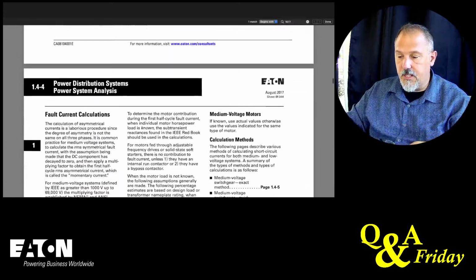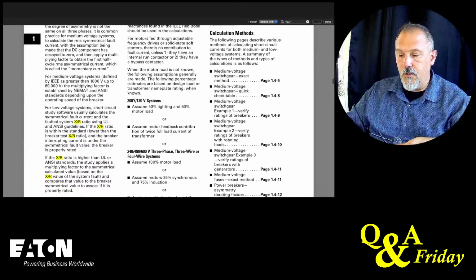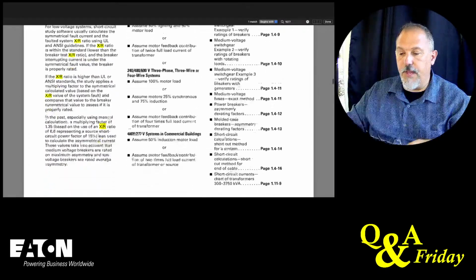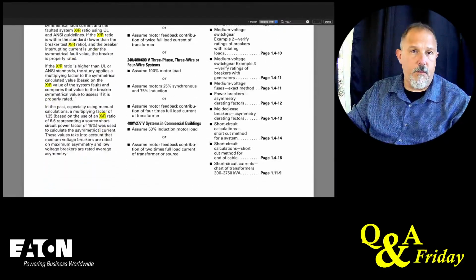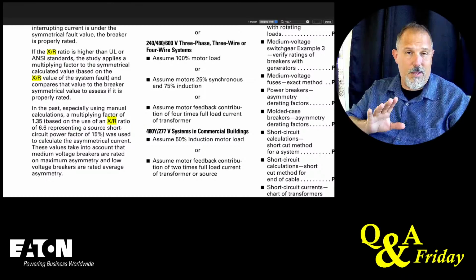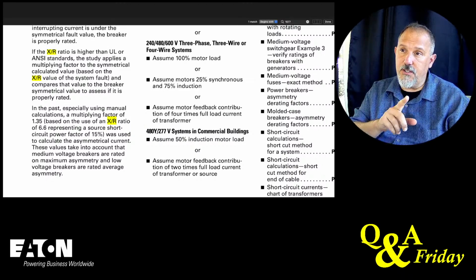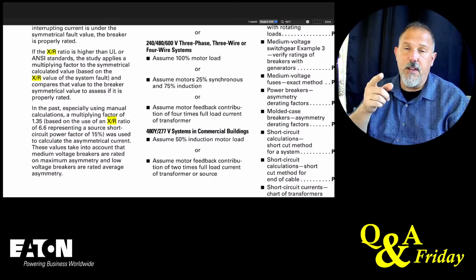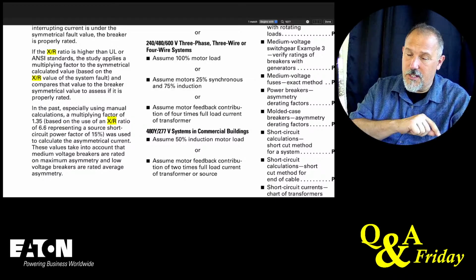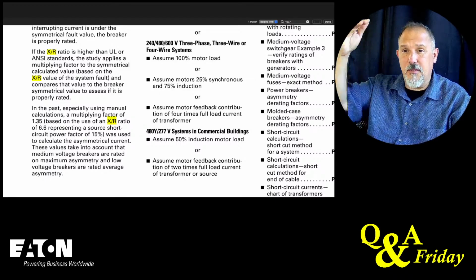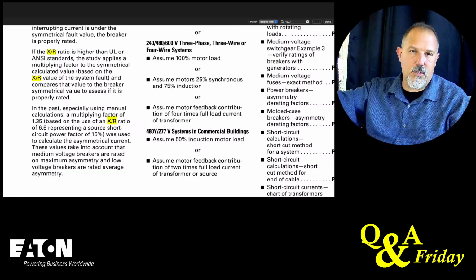And so in some cases, we will give you a value that is a little bit bigger of a fault current than what you need, which is okay. Or if you're doing arc flash calculations, I might give you an available fault current that's a little lower than what you can expect. And, oh, by the way, I'm going to give you a little bit longer clearing time. Different story, different day.